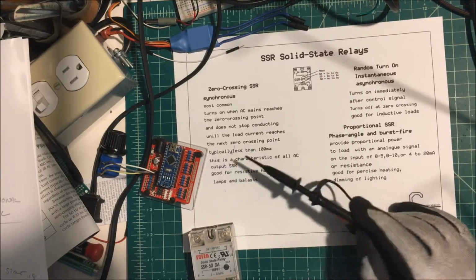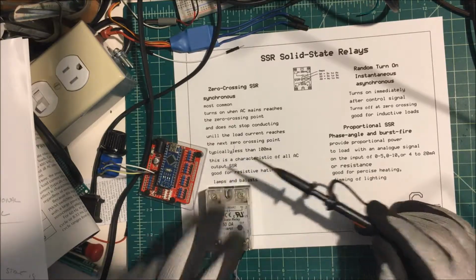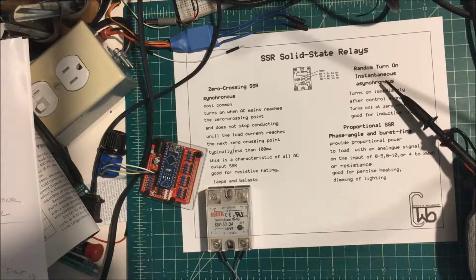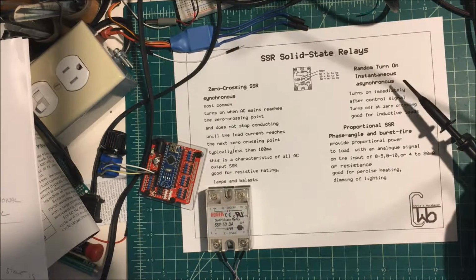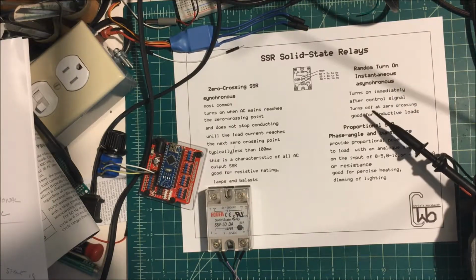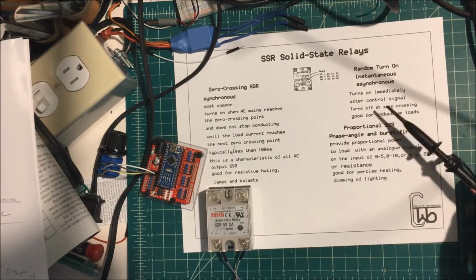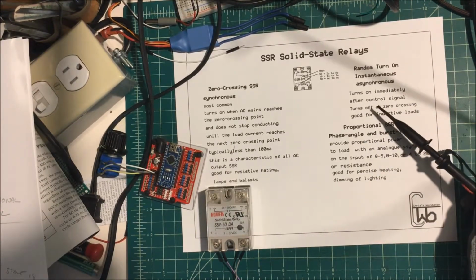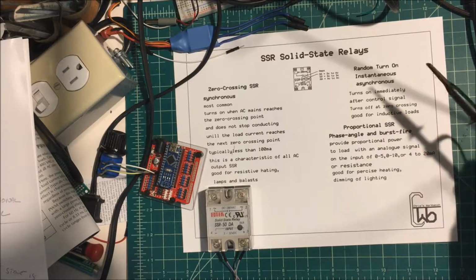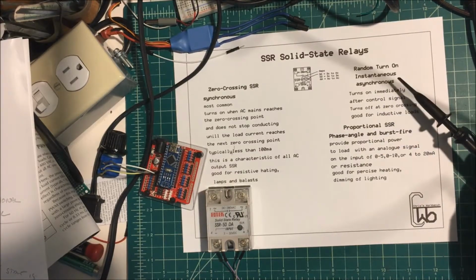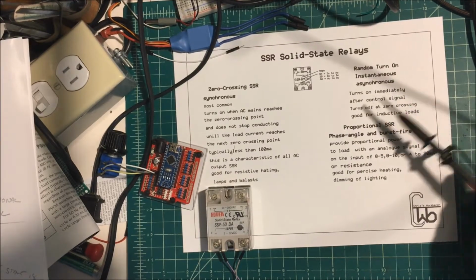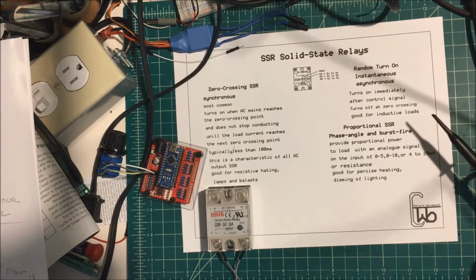Now we have these random turn-on, instantaneous or asynchronous relays, and they turn on immediately. As soon as you apply a signal to them, they turn on, whether it's at zero volts or all the way up to the peak voltage of the sine wave. And those are good for inductive loads.